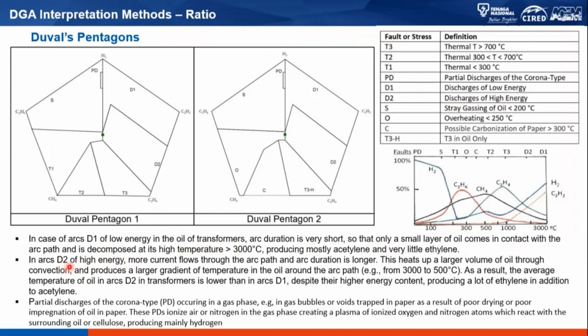Whereas D2, or high energy discharge, normally involves arcing that comes with follow-through current, which is quite high but at a longer duration. One interesting point highlighted here is that this follow-through current will heat up a larger volume of oil through convection and produce a larger temperature gradient in the oil around the arc path.